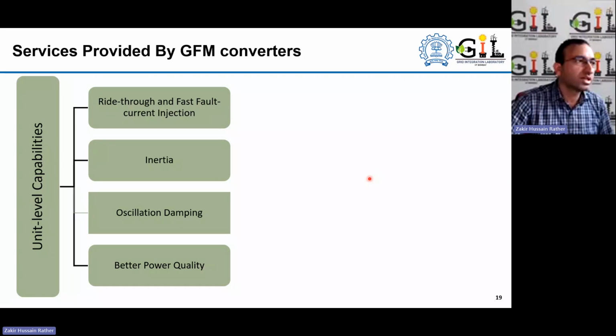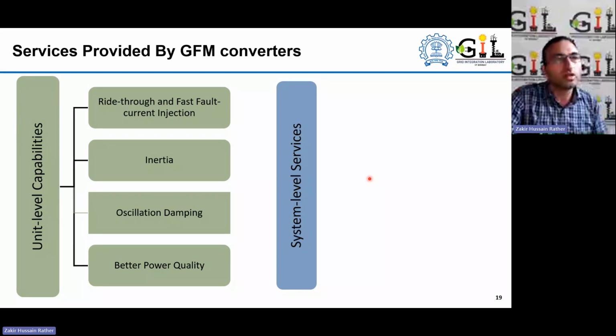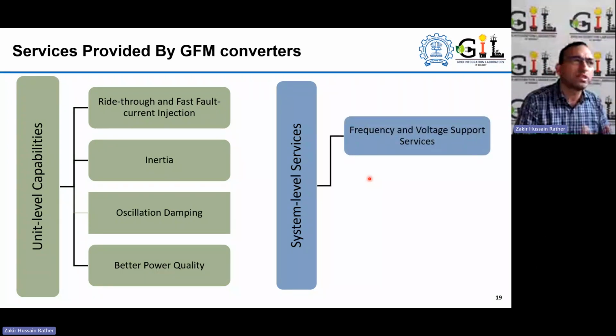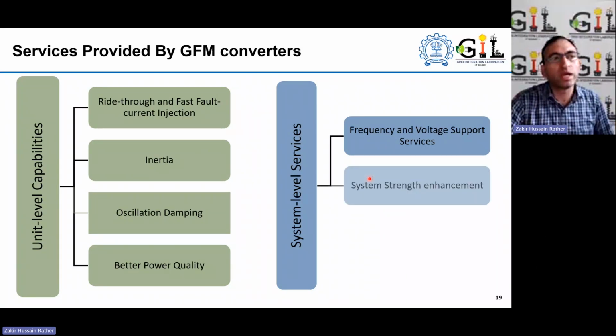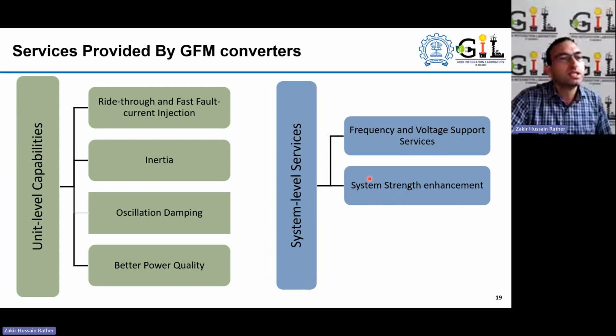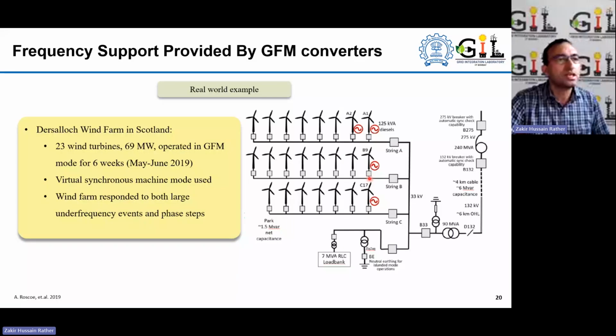They can actually be used to improve the quality compared to grid following technology. That is at the unit level. Now, if you look at the system level, of course, the services that are being provided at the system level stem from the unit level also. So it's all linked. So at system level, they can provide the frequency and voltage support services. Not that grid following technology does not provide. They do have the capability and they do provide even as of today as well. But the frequency and voltage support capability of this grid forming technology is relatively better than grid following technology. System strength enhancement, as I mentioned earlier, at the system level, it can provide the black start services as well.